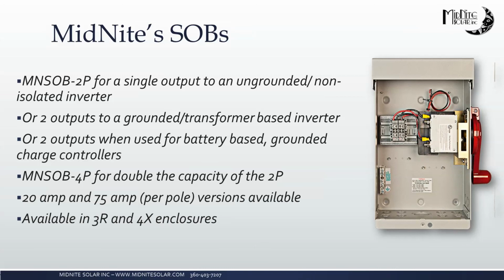We'll talk about the SOBs. We call these the shutoff boxes. They're available in a 2-pole or a 4-pole. And what we mean by pole is how many strings or how many poles of the switch do we have. So in the picture here, you'll see we have a red in and a red out, a black in and a black out. This could work for a single 600 volt string into a grid tie inverter. If you use a 75 amp version, this could work as 2 separate 300 volt charge controllers, for example. The 4-pole would have twice as many terminal blocks.